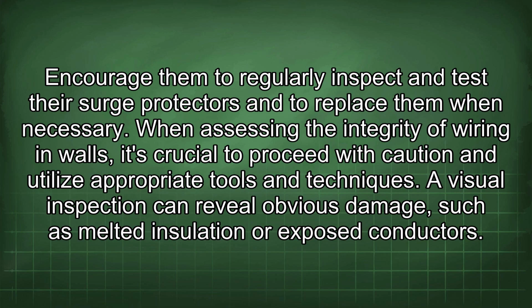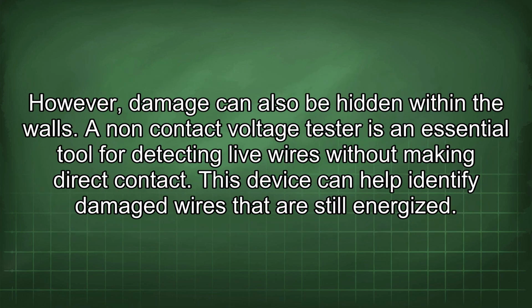When assessing the integrity of wiring in walls, it's crucial to proceed with caution and utilize appropriate tools and techniques. A visual inspection can reveal obvious damage, such as melted insulation or exposed conductors. However, damage can also be hidden within the walls. A non-contact voltage tester is an essential tool for detecting live wires without making direct contact. This device can help identify damaged wires that are still energized.